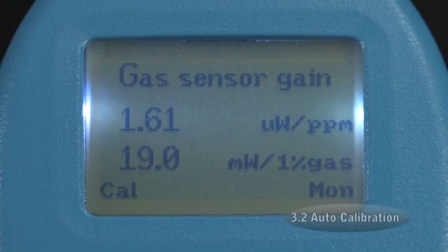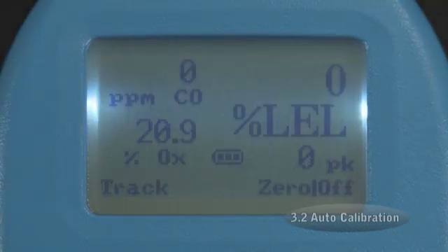Once you have finished calibrating all of the sensors, press the right button under the letters MON to display sensor gains. Sensor gains are used to predict the remaining life of the sensors. From here, press MON again to switch to the monitor mode, where you may start using the instrument or turn it off.